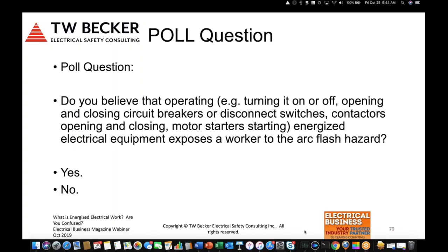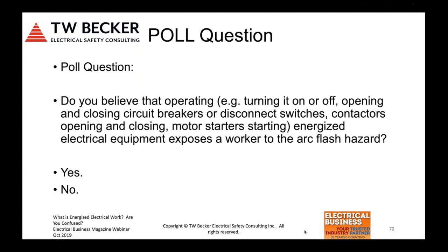So again, this is one of the myths and misinformation that I believe are out there, and it's something that we're going to have to work on in industry. It's a trend that I don't know why we're going in this direction. It does relate to the condition of maintenance discussion, but again, operating energized electrical equipment doesn't expose a worker to the arc flash hazard unless there's an abnormal condition, right? So again, I encourage you to ensure that you do a reasonable risk assessment when deciding to put arc flash PPE on workers that just operate energized electrical equipment. Doors closed, covers on, normal operating conditions, I don't believe we need arc flash PPE on workers on a work site.